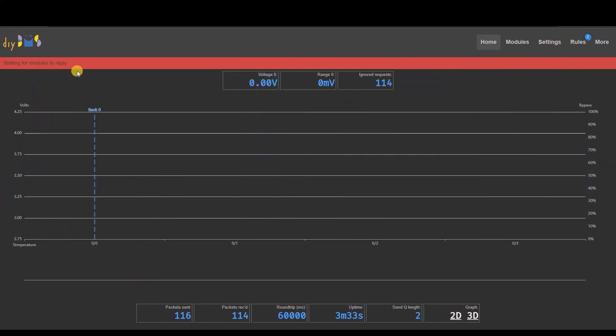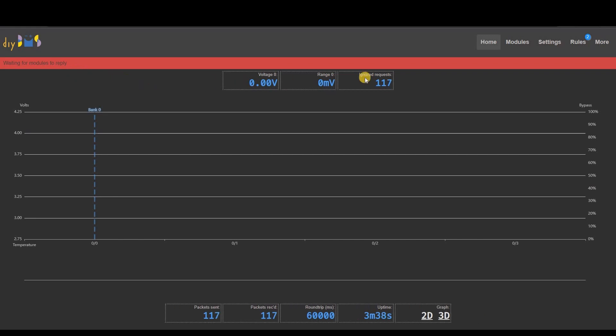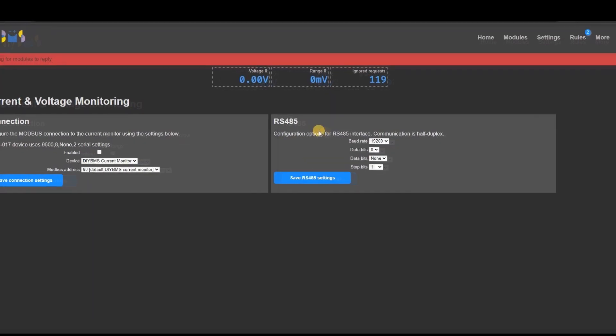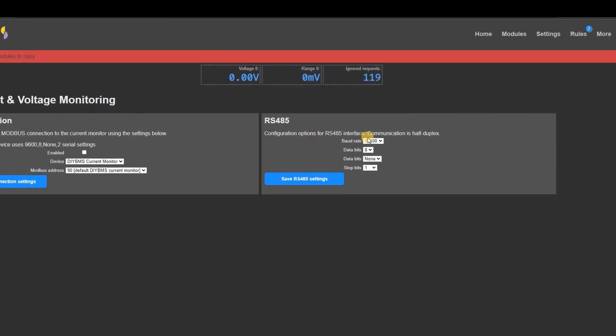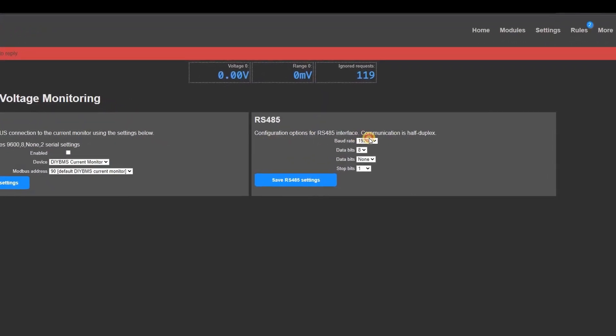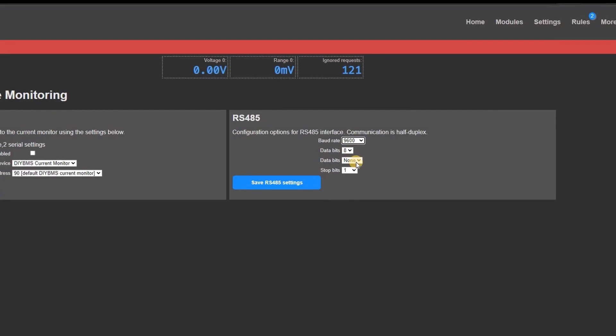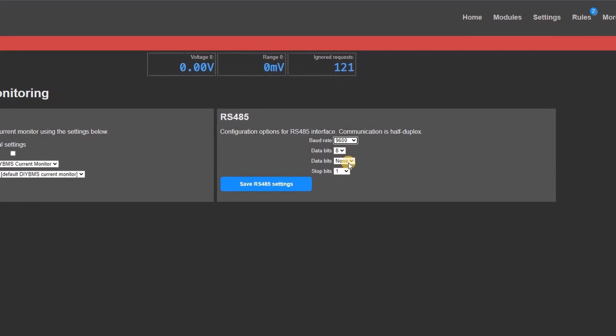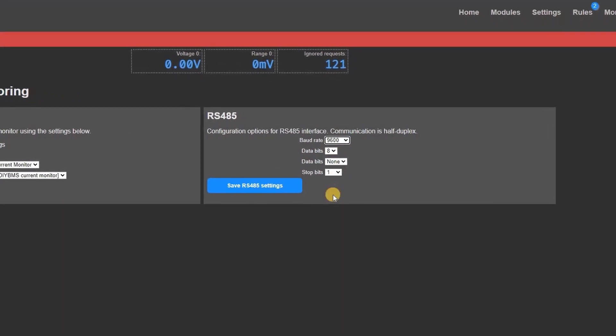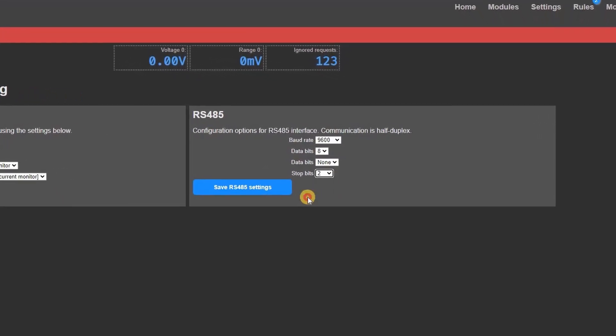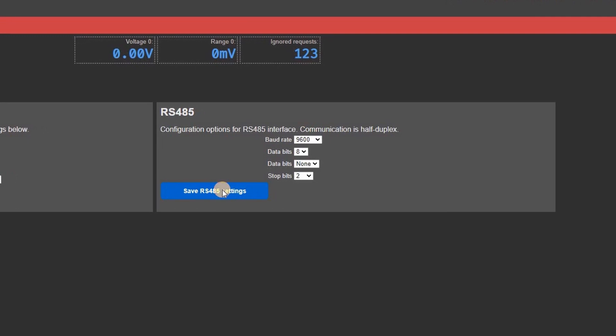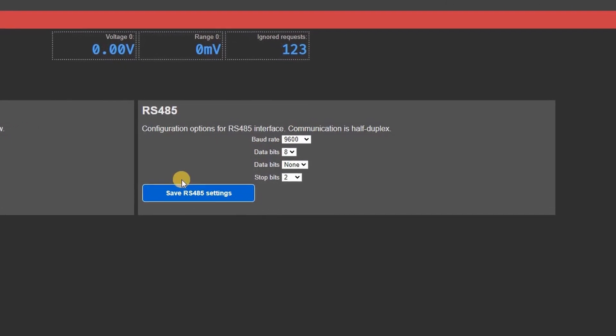To configure the current monitoring open up the current monitor settings page. Change the RS485 options to use 9600 speed, 8 data bits, no parity and 2 stop bits. Then click save and then wait a few seconds for the page to reload.